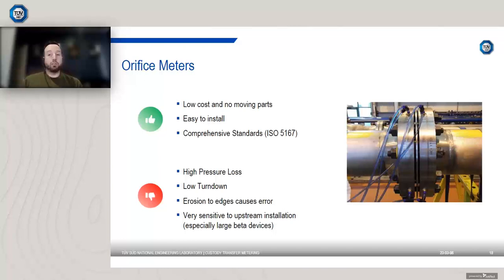One of the biggest advantages is that there are comprehensive standards available. ISO 5167 is a really mature standard, and you can use it to calculate the discharge coefficient. A big advantage is that if you manufacture the plate to the tolerance of the standard, you can use it without calibration. So these are very popular for gas systems. Some of the downsides are that, by their nature, they create a restriction in the flow. So there is a pressure drop, and depending on the flow rate, they can induce quite a high pressure loss in the line.